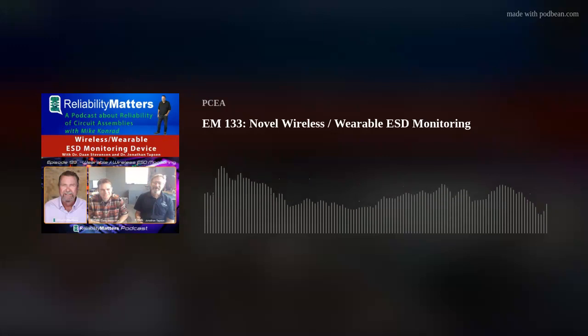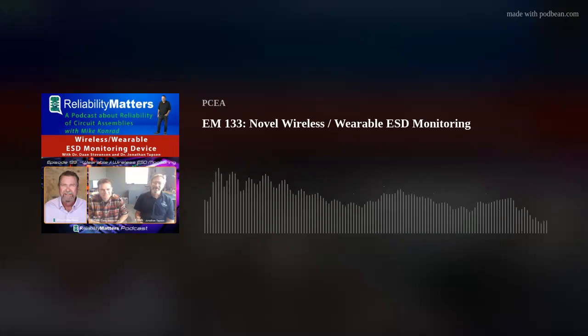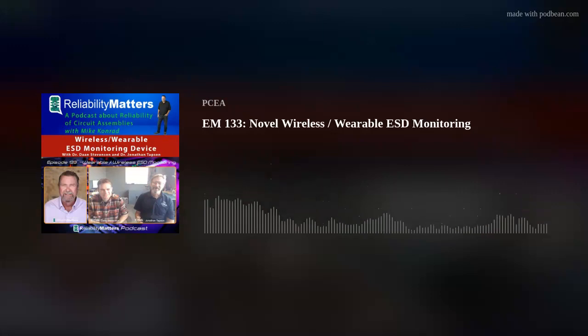then there's this idea that you can detect bad equipment. The very first place when we went on site to do our very first beta test, we put this on a guy who had told us that his facility had a very high ESD standard, and he genuinely believed that. And he came back 10 months later and said, "I just realized that my own personal wrist tether has been broken internally for I don't know how long. It looked fine, and your device told me that my voltage was fluctuating all over the place when I was tethered." So that kind of intuition.